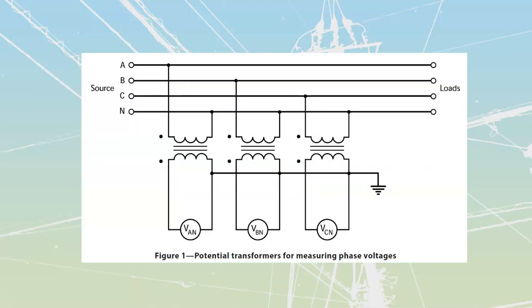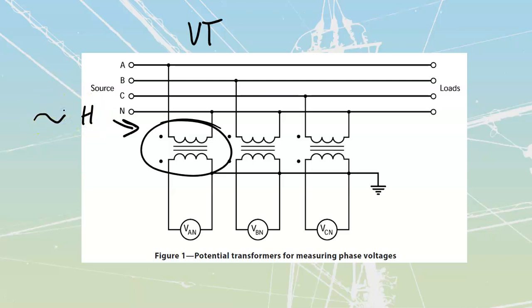We're going to start by talking about PTs, and PTs are also sometimes going to be called VTs. PT or VT stands for potential transformer or voltage transformer. They're a special type of precision transformer that, based upon the high side voltage you place in, so they come in a range of high side voltages, you are always going to have a low side voltage of 120 volts that comes back out of these things.